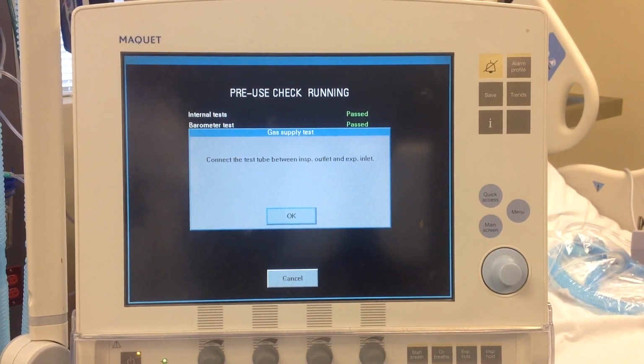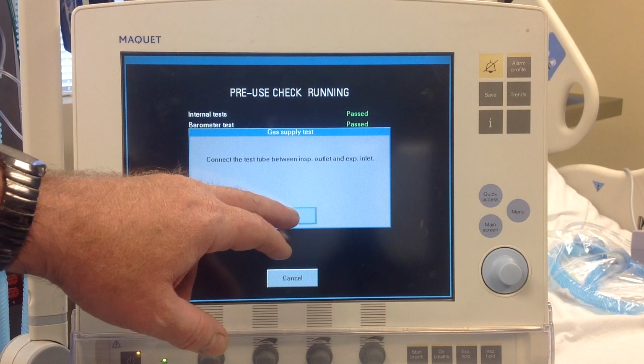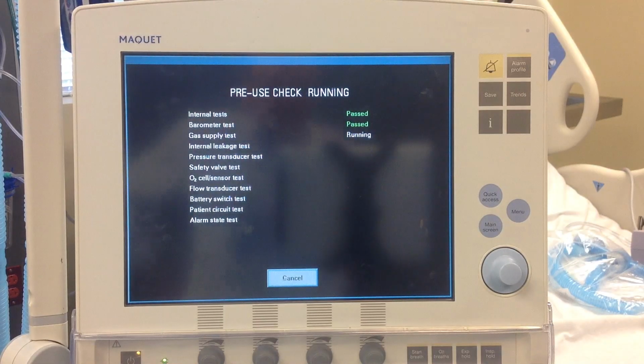Okay, connect the tubing. I have connected it between my output from the ventilator and my return on the exhalation cartridge. Hit OK. And then it is just a matter of waiting. If you notice, the 840 asked what we were calibrating. Were we calibrating an infant circuit, pediatric circuit, adult circuit? What were we doing? The Maquet Servo I does not matter.